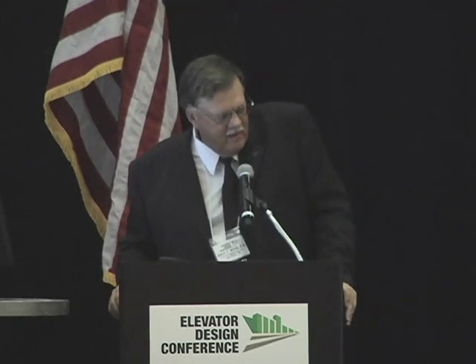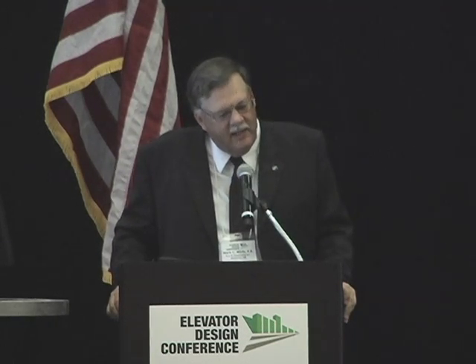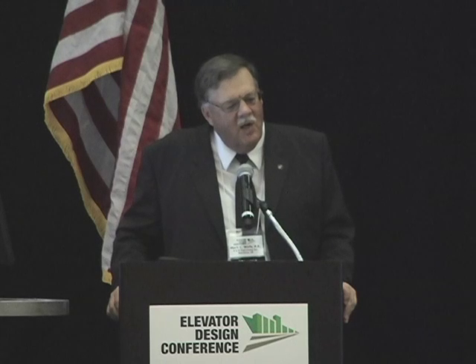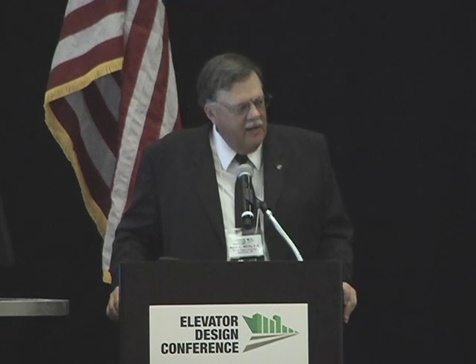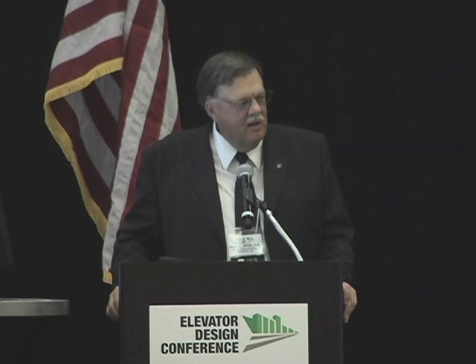The question is on VFD drives, if there's any special provisions or whatever for lockout and tagout. Okay, lockout and tagout in NFPA 70E, you lock out the breaker. A control circuit stop lock is not a lockout. It's not legal. It's not an appropriate lockout. The only legal lockout is the main 480 volt or 230 volt power source to the drive. And it's the same as it's always been.